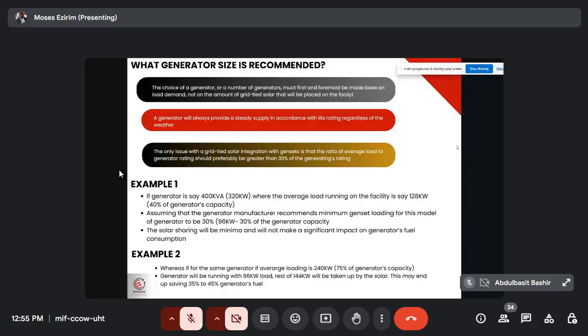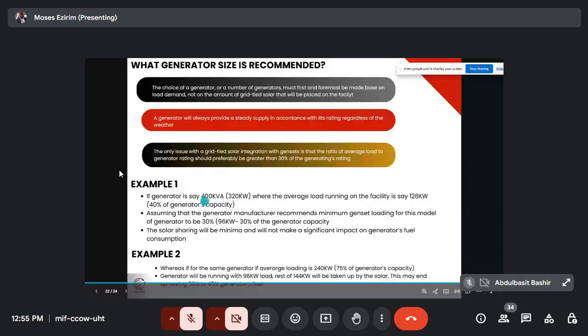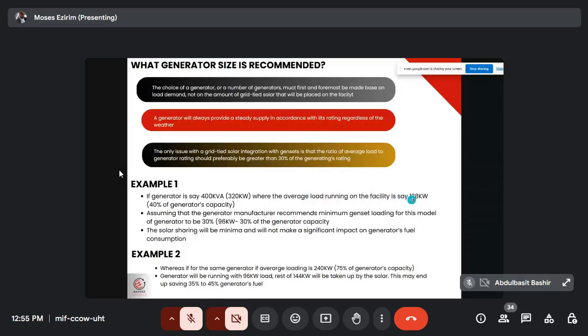So that means the average load that you want to size must be greater than the recommended percentage. Now, let's take an example. If the generator is rated 320, and the average load running on the facility is 128 kilowatt, that's 40% of the capacity. Assume the generator manufacturer recommends a minimum genset loading of 30%, that's 96. The solar sharing will be minimal.